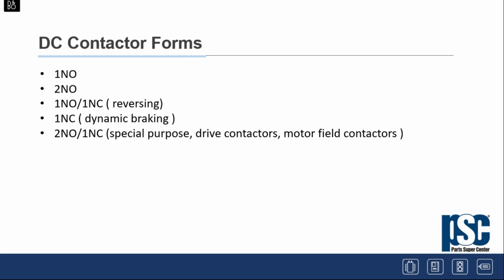Okay, on DC contactors, there's basically 5 different forms that are commonly used. The one normally open, where you're breaking just one pole of the DC circuit; 2 normally open, where you're breaking both the positive and negative side of the DC circuit. Then you have the 1 normally open and 1 normally closed variety, which is primarily for reversing; 1 normally closed, which is dynamic braking. And then you have a 2 normally open, 1 normally closed, which is special purpose, frequently used in drive contactors or synchronous motor field contactors and some other similar applications.